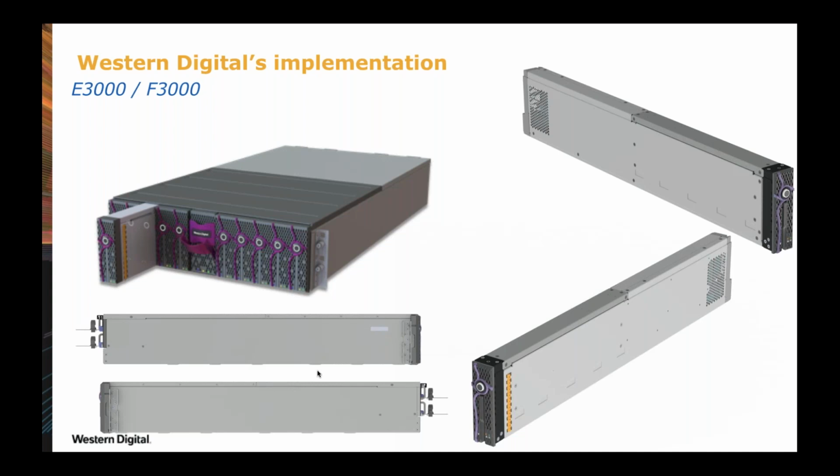If you want to have this as an open standard, I really think you have to have the airflow patterns that would go through this. If all sleds were the same, do you have any baffling between them? What is the guaranteed CFM? Things like that would make it easier for someone to design a module. Without that, I don't see successful third-party adoption of this to build these modules. But even if the module was self-contained for its cooling, the air still has to be there on the inlet and has to be exhausted on the outlet, and there's system level planning to be done for that.